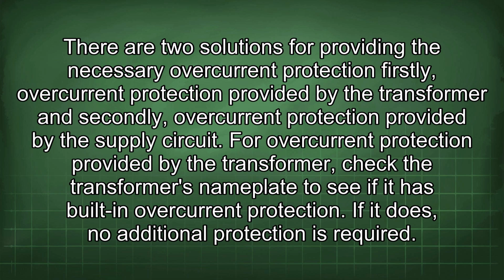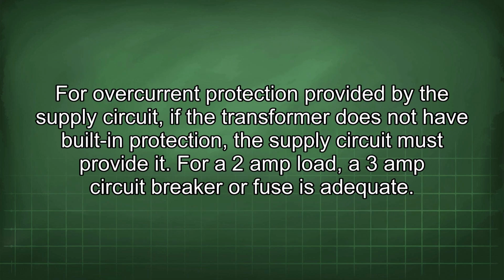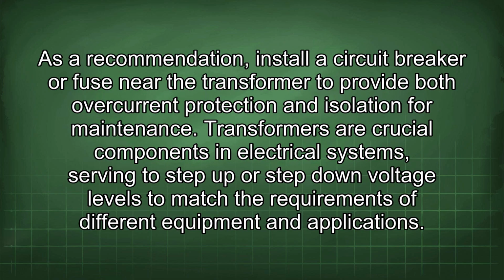For overcurrent protection provided by the transformer, check the transformer's nameplate to see if it has built-in overcurrent protection. If it does, no additional protection is required. For overcurrent protection provided by the supply circuit, if the transformer does not have built-in protection, the supply circuit must provide it. For a 2 amp load, a 3 amp circuit breaker or fuse is adequate.